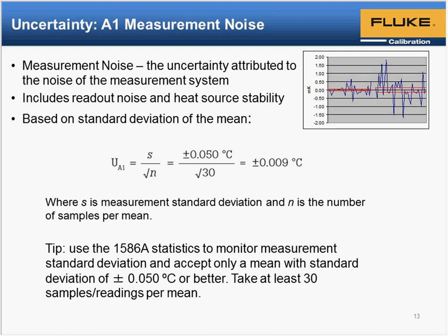Laboratories, though, will not necessarily have a measurement noise limit. They'll measure the samples, compute the mean and standard deviation, and directly enter the standard deviation that is measured at that point in time. And that's certainly an acceptable practice too. It would be important in that scenario to make sure that it's clearly understood what typical performance is, in case the system is not working correctly and the noise is significantly larger.